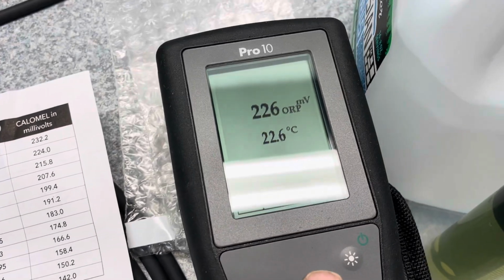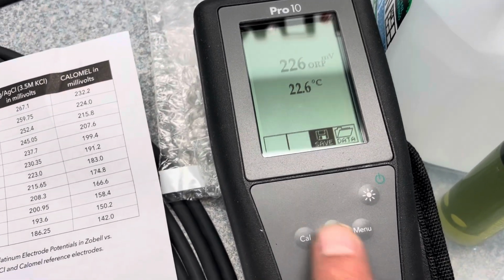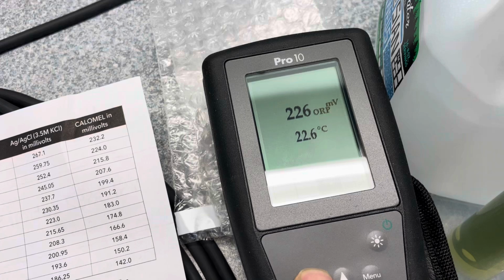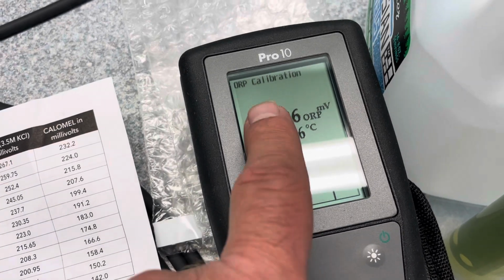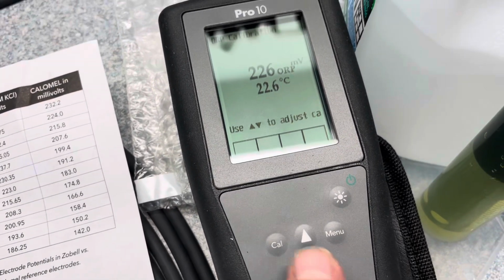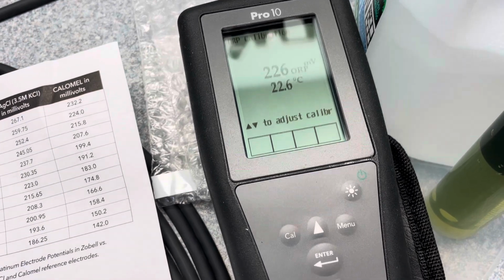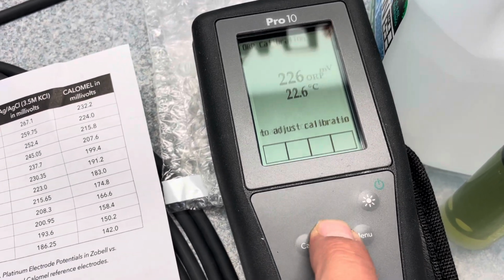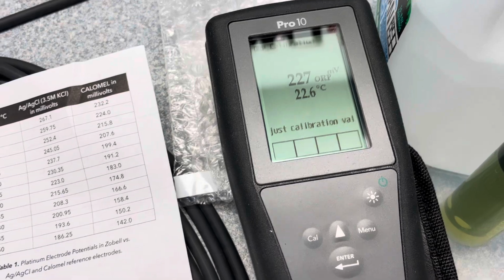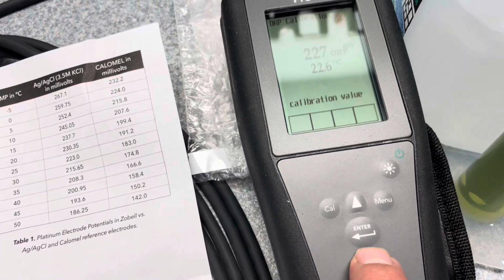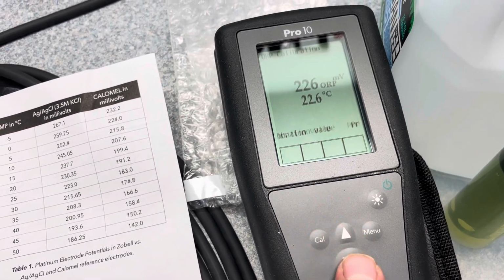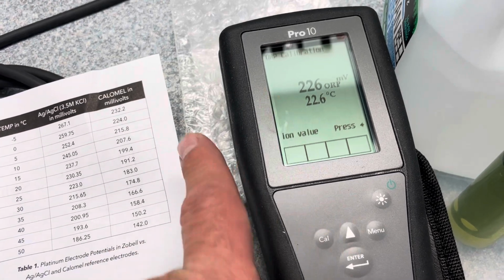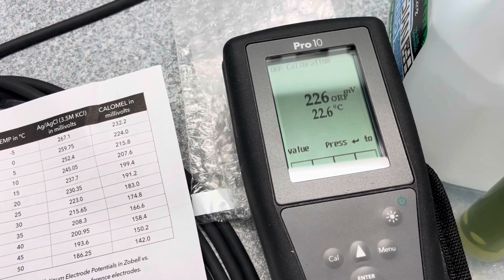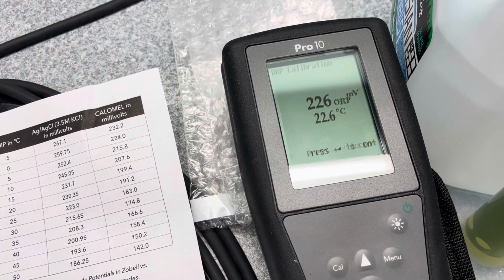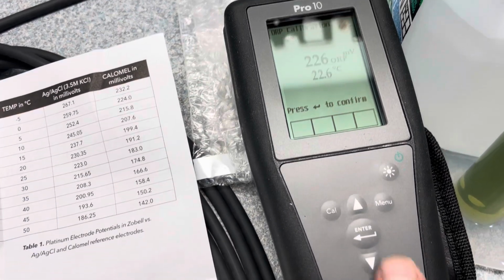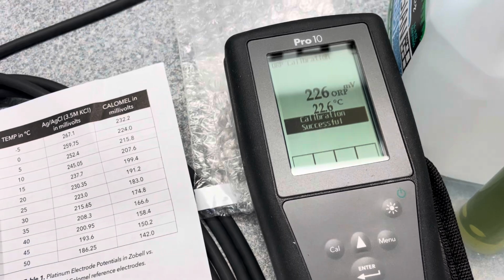And even though that's where we are right now, I'm going to walk you through the calibration. Simply hold down Cal, and then the screen says ORP calibration, and use the up and down arrows to adjust. So if it was not on already, you would just go up or down to adjust so your millivolts will match what you have decided to calibrate with your calibration chart. So once we have that, we're just going to simply hit the enter button.